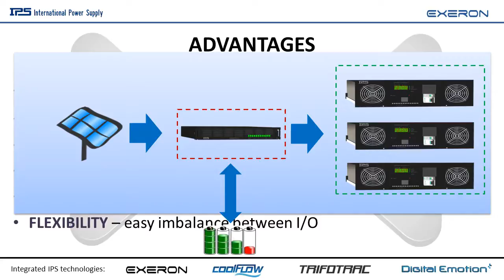Now let me materialize all the good things we said about EXERON and see how it looks. This is an example configuration of EXERON MX. Here is the section for the PV and MPPT controllers, in this case 6. We have also 6 AC chargers. Here is the inverter section with 3 inverter modules in this case, the MCU, the main control unit, and in the upper part is the PDU, power distribution unit, where all input-output connections, switches and protections are located. So there is no need to buy any additional distribution equipment like power boards, fuses, or circuit breakers.